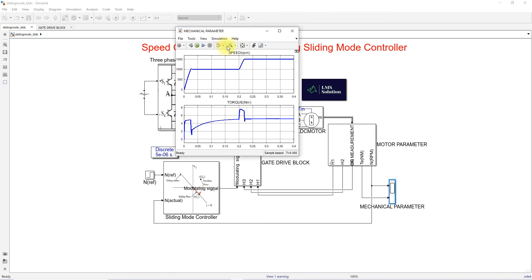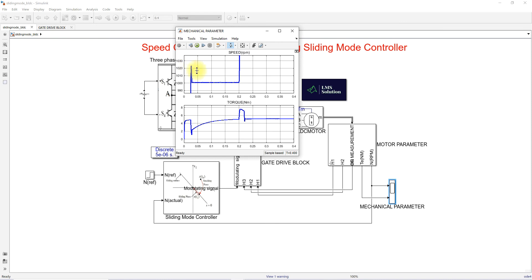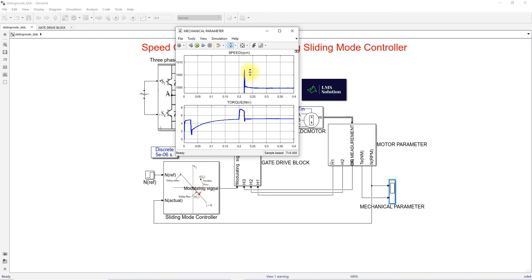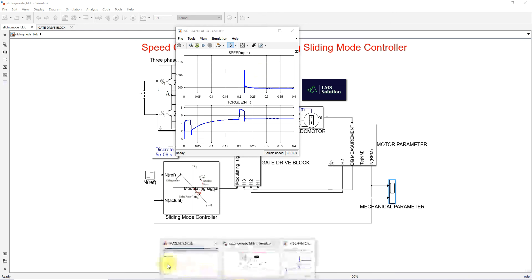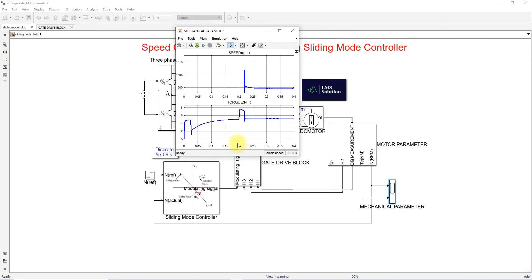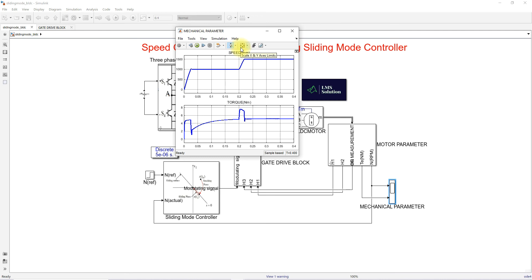I am going to zoom in a little bit. Initially we are having an overshoot of around 20 RPM. When operating at 1500 RPM, we are getting an overshoot of around 6 RPM. That means 20 divided by 1000 is around 2% overshoot, and 6 divided by 1500 is 0.4% overshoot.